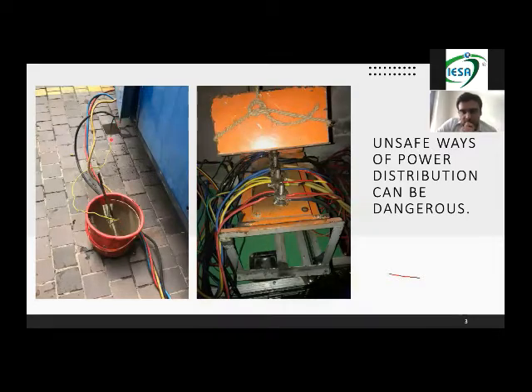So imagine that if you're having a 60 kilowatt genset, your neutral size is half, which is 30 kilowatts. If you're using this kind of wire, and there is any unwanted current over here, if the wire size is so small, this wire can't take it to the ground. You need the right size of earthing wire to take it inside the ground. That is why the earthing is important.